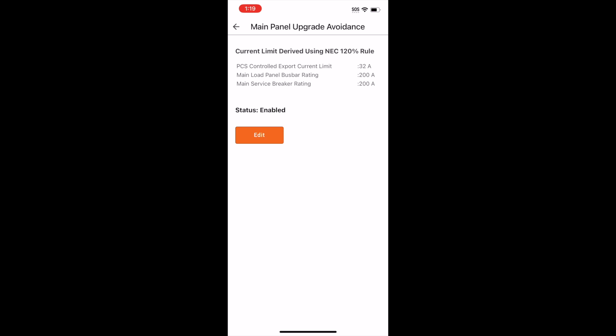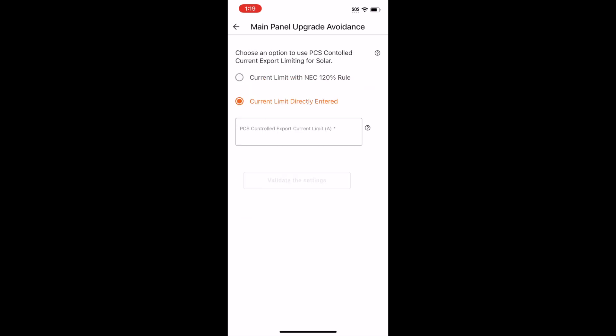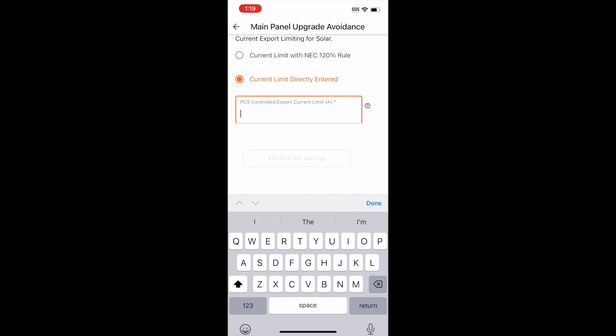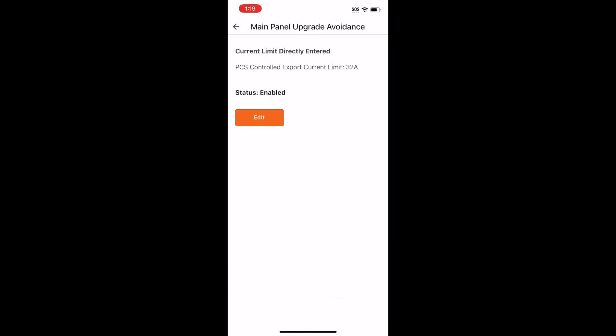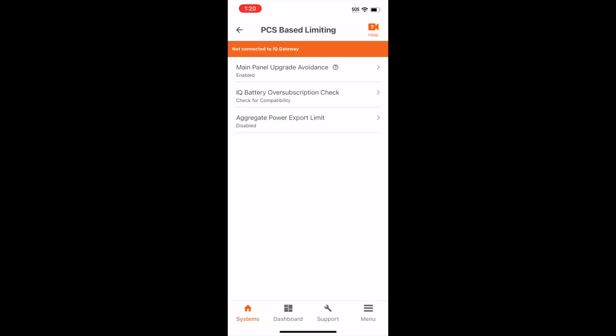Another option is Current Limit, directly entered by you. You specify the current limit number, and the system uses that specification. It's important to know that your system will soon be configured to use these system details, but they are not yet implemented into the functional system. Be sure to fully commission the system for the PCS limits to take effect.